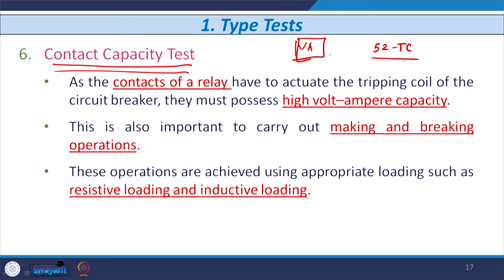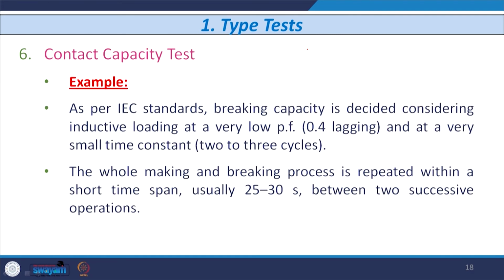This is also important for carrying out making and breaking operations by the relay contacts. If the relay contact is normally open, then how many breaking and making operations it can perform needs to be defined by the manufacturer. These operations are achieved using appropriate loading; you can use resistive loading or inductive loading. Normally inductive loading is used, and resistive loading is not used. For example, as per the IEC standard, breaking capacity is decided considering inductive loading at a very low power factor, say 0.3 to 0.5, and a very small time constant of 2 to 3 cycles.